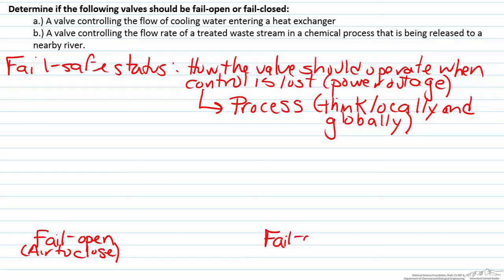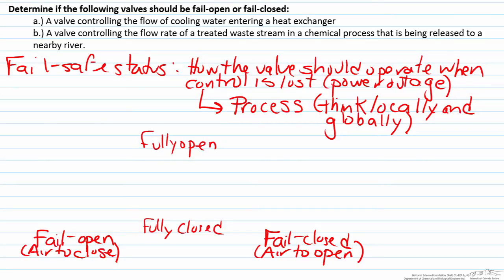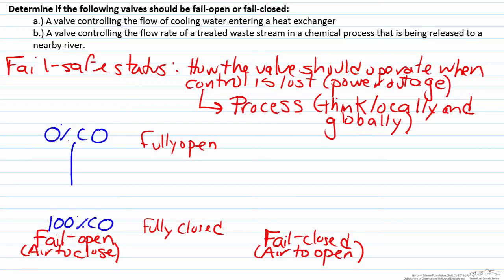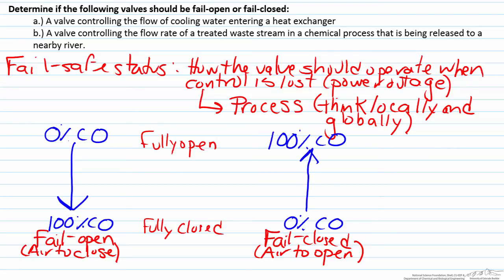The second option is a fail closed valve, also known as an air to open valve. For a fail open valve, we want zero percent controller output to correspond to the valve being fully open, because if all power is lost the controller defaults to zero percent. A hundred percent controller output corresponds to fully closed, so controller output increases as the valve closes more. For a fail closed valve the opposite is the case: zero percent controller output means fully closed, and a hundred percent means fully open — an increase in controller output opens the valve further.